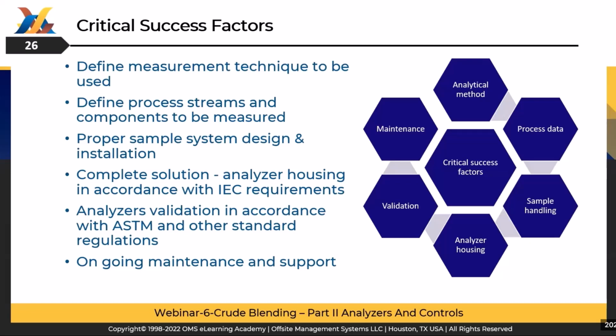Define process streams and components to be measured, proper sampling, system design and installation, complete solution, analyzer housing based on project specifications or standard requirements, analyzer validation per ASTM and other standard regulations, and how validation should be performed. Is there any local customer requirement for performance validation? It's better to agree on these terms before the commissioning. It has to be agreed with the end user. And of course, ongoing maintenance and support.